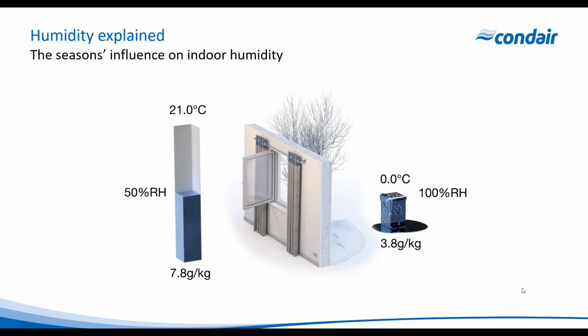So we know, certainly in many applications, if we're with set points at 21 degrees C and 50%, when there is the potential for outdoor air to be below 10.5 degrees C, we are going to have a humidification demand in the space, because as we put that outdoor air into the indoor space, we don't have the absolute moisture content in the air to be able to meet the set points in the space.